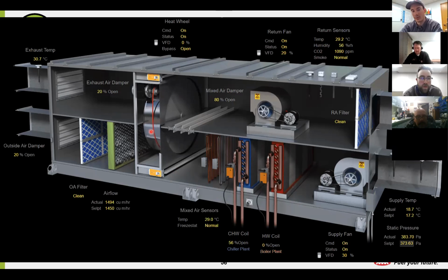We have a heat recovery wheel here. I'll go into that more specifically, but that's just a way to save energy when we're exhausting air. We don't want to just lose all that heat that we paid to condition. We've got our outside air. We've got exhaust. We need to get rid of air in the building. And then we've got our supply fan, and that's the tempered air going into the space.